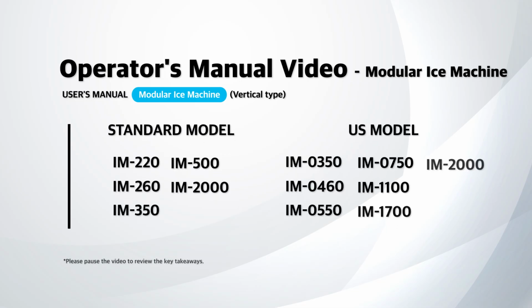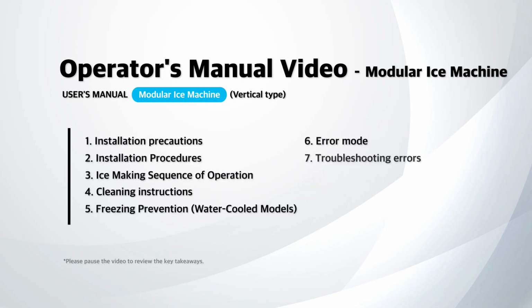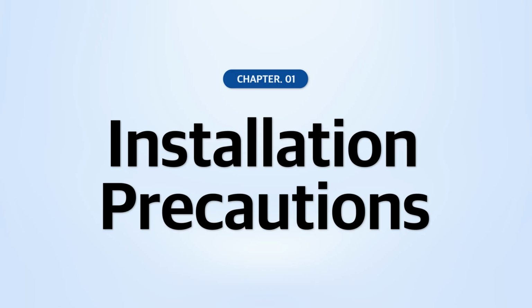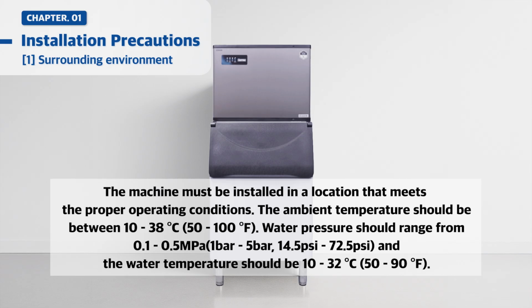This is the manual video for the modular ice machine. The machine must be installed in a location that meets the proper operating conditions. The ambient temperature should be between 10 to 38 degrees Celsius. Water pressure should range from 0.1 to 0.5 megapascal, and the water temperature should be 10 to 32 degrees Celsius.